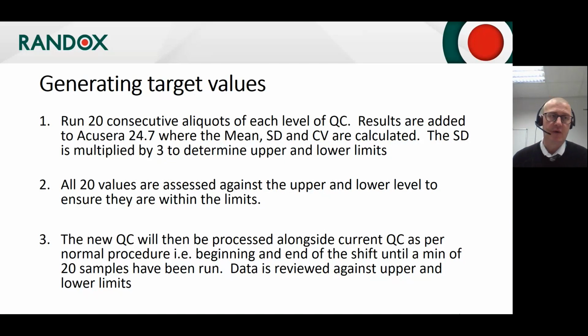We then do an inter-precision run, which is processing the new QC alongside the current QC as normal routine procedure, i.e. at the beginning and at the end of each shift, again until a minimum of 20 samples has been run. This data is then reviewed using the same process as above, and this data will represent the systematic bias of individual assays. This process usually takes between 10 and 20 days.